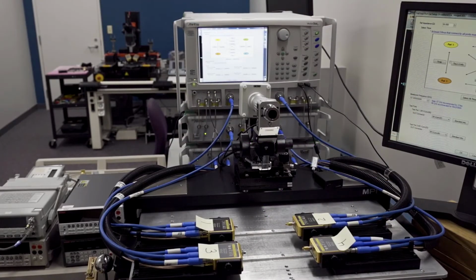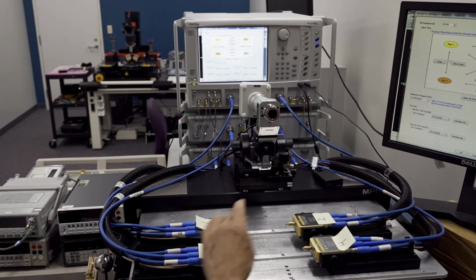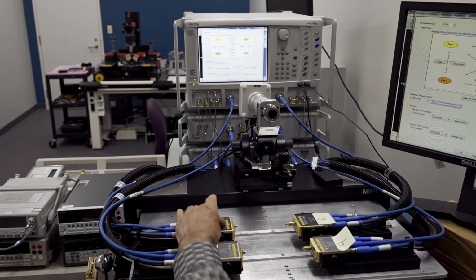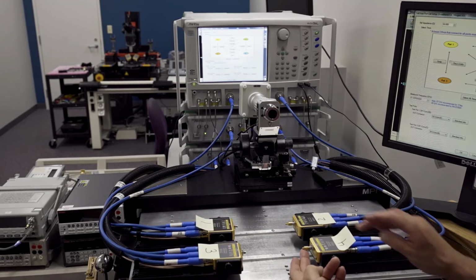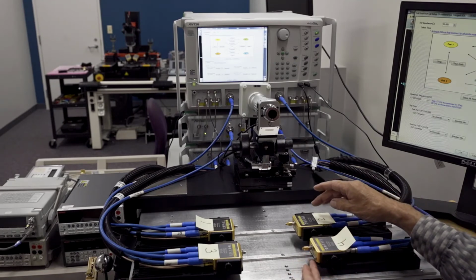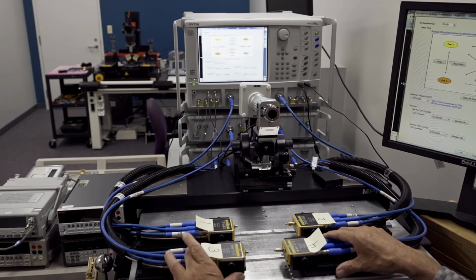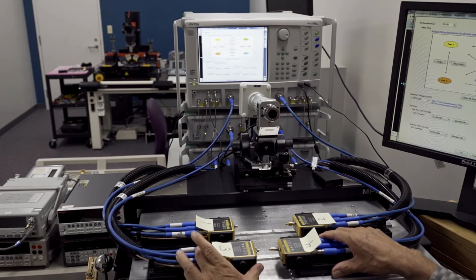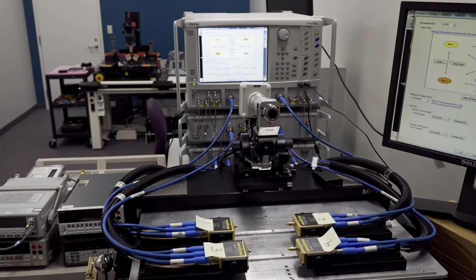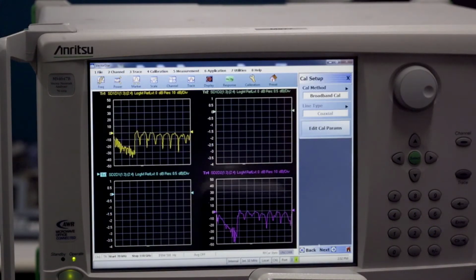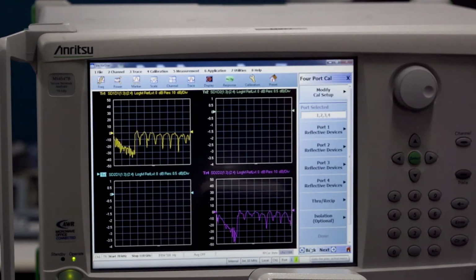So here we have the setup for our 4-port measurements, and we have the 4 modules with 1 millimeter test port connectors. We have the male on ports 1 and 3, and then we've added these adapters for ports 2 and 4 so that we now have an insertable through situation, which is why we configured our throughs to be 0 length.